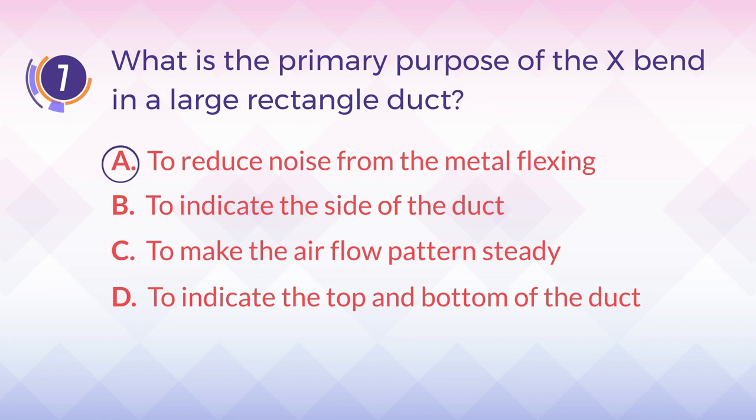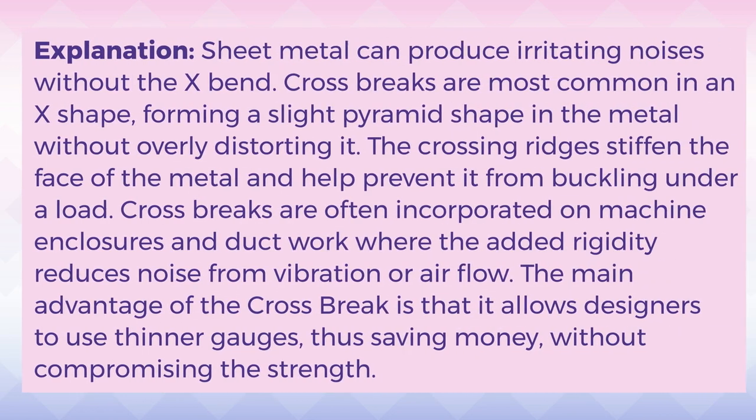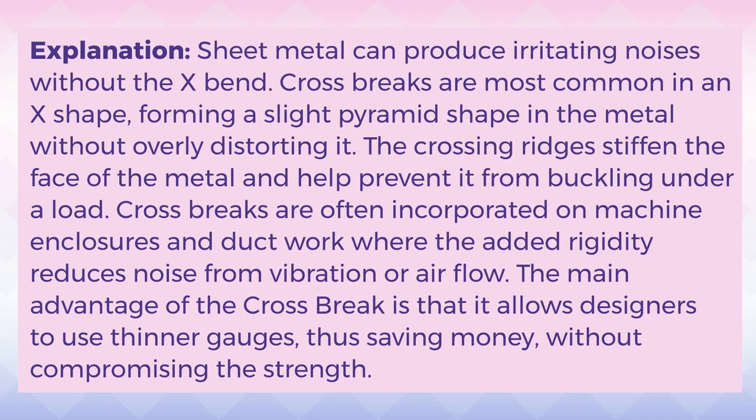The answer is A. To reduce noise from the metal flexing. Explanation: Sheet metal can produce irritating noises without the X-Bend. Cross breaks are most common in an X-shape, forming a slight pyramid shape in the metal without overly distorting it. The crossing ridges stiffen the face of the metal and help prevent it from buckling under a load. Cross breaks are often incorporated on machine enclosures and ductwork, where the added rigidity reduces noise from vibration or airflow. The main advantage of the cross break is that it allows designers to use thinner gauges, thus saving money, without compromising the strength.